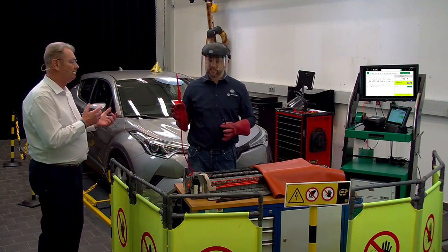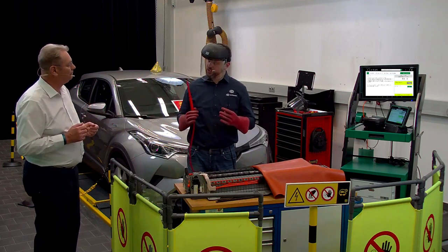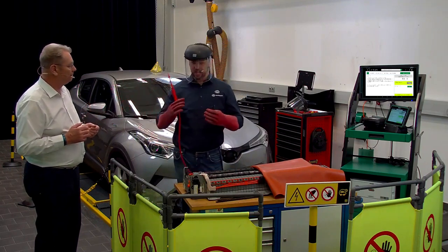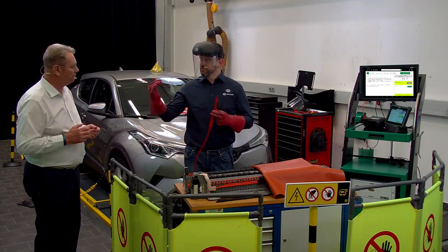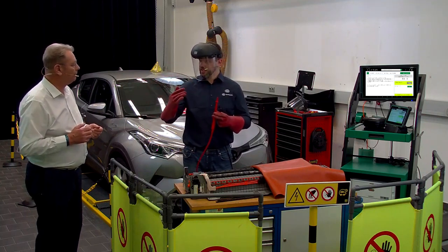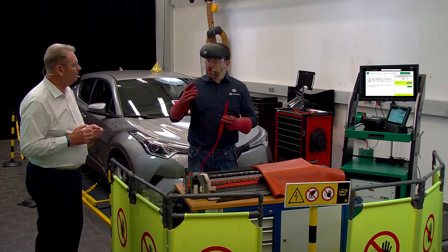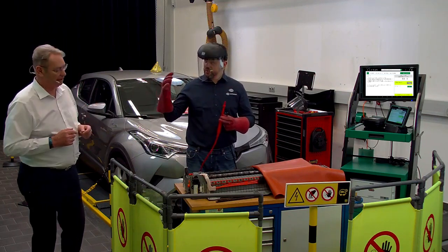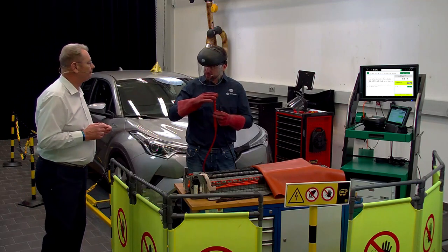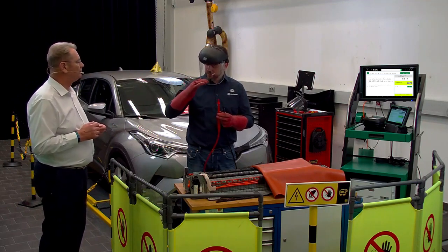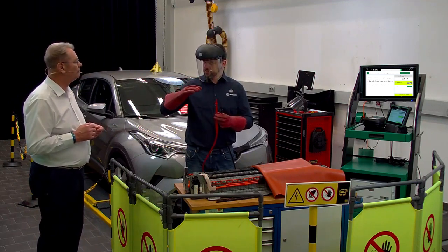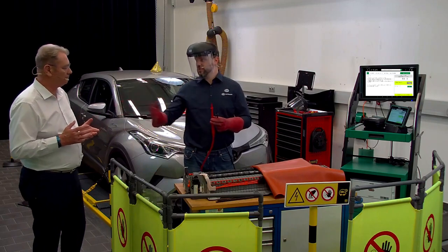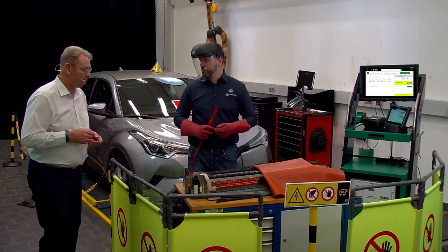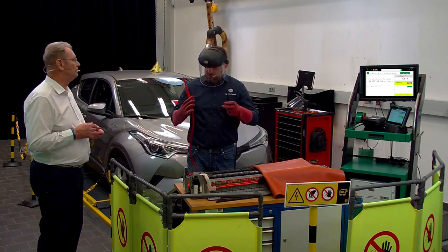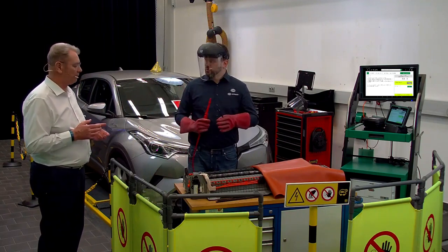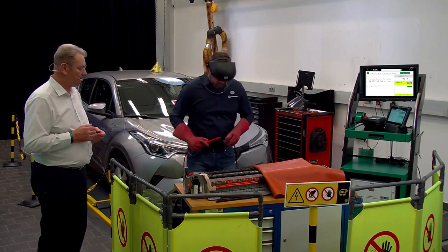Yeah, this is different. Depending on the function, in the guided measurement you get an automatic evaluation. Green, yes. Red, faulty. In this case, you have to decide. So the test probe check is green. The system says okay. After that, each part is with a gray mark. It's up to you. You are the responsible person, or I am the responsible person for this evaluation, to decide what is necessary. So we start now with the measurement.